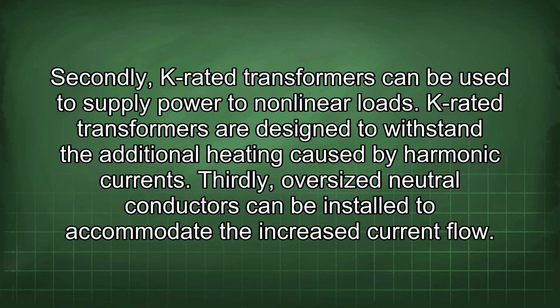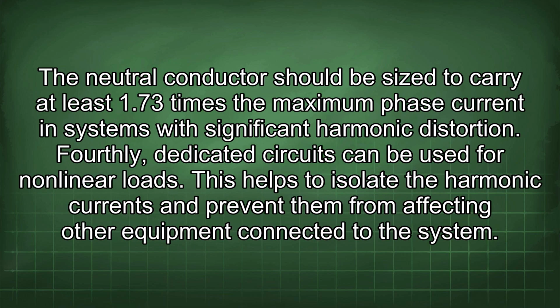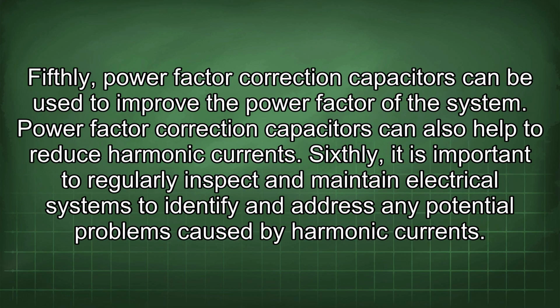Secondly, K-rated transformers can be used to supply power to nonlinear loads. K-rated transformers are designed to withstand the additional heating caused by harmonic currents. Thirdly, oversized neutral conductors can be installed to accommodate the increased current flow. The neutral conductor should be sized to carry at least 1.73 times the maximum phase current in systems with significant harmonic distortion. Fourthly, dedicated circuits can be used for nonlinear loads. This helps to isolate the harmonic currents and prevent them from affecting other equipment connected to the system. Fifthly, power factor correction capacitors can be used to improve the power factor of the system. Power factor correction capacitors can also help to reduce harmonic currents.